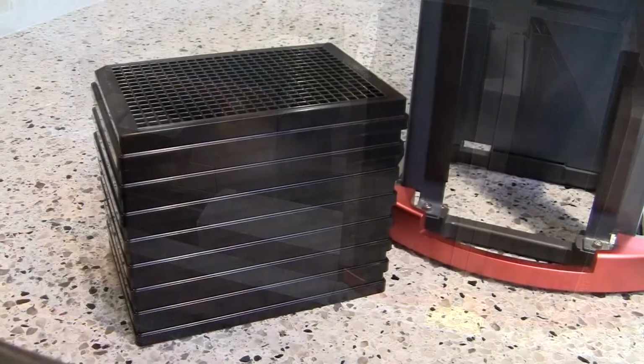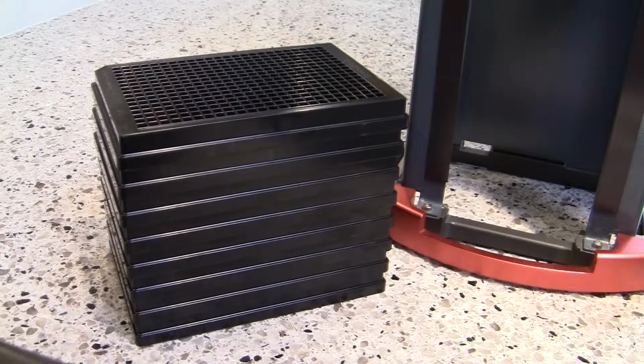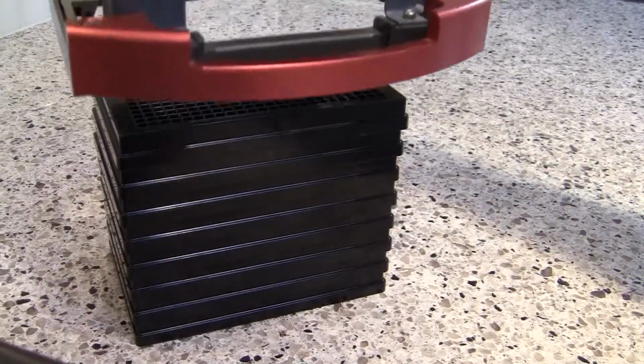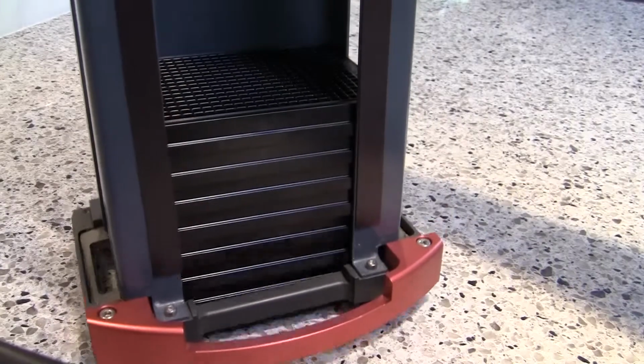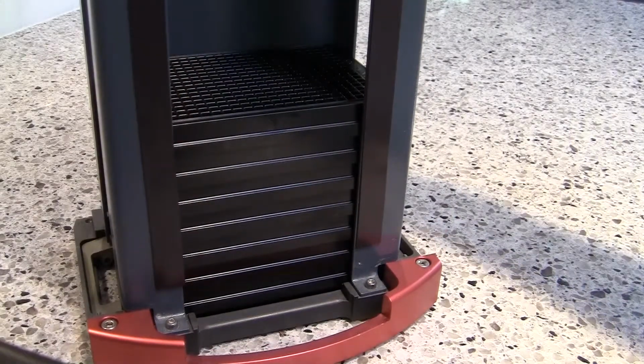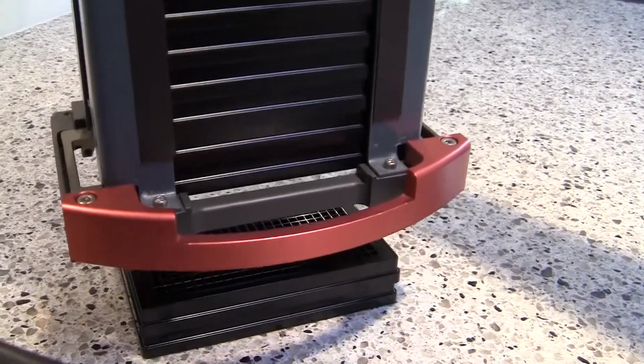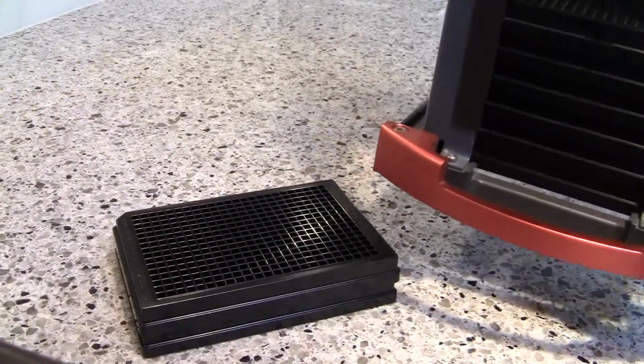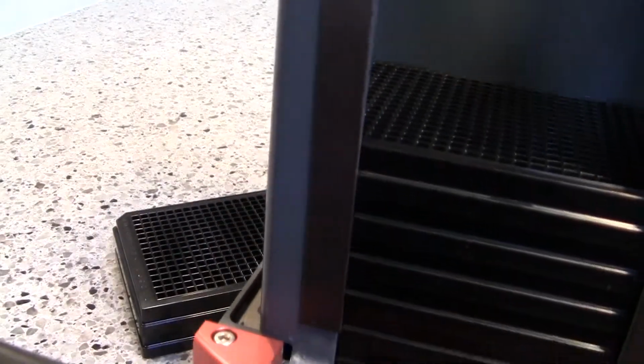An alternate and somewhat faster and safer way to load plates is to position them on a flat surface like so and slip the stack down over the top. In this case, two dummy plates were used at the bottom. You may need to use one or more depending on the type of plate you have.